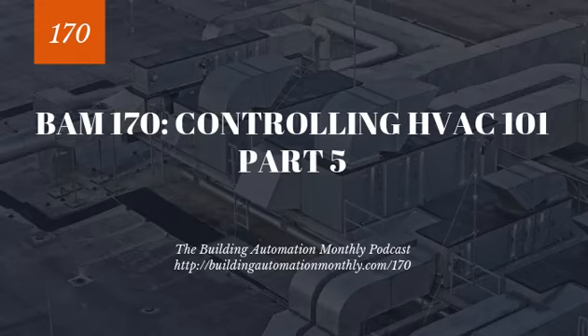That's why we put in mixing valves, and that's also why we put in VFDs on our secondary pumps, so that we can control pressure and we can also control flow into the secondary loop so we don't have this issue. It's really important that you understand this, especially if you're dealing with decouplers or variable speed drives on the secondary and you're not properly controlling your mixing valve, because you can get into that issue.